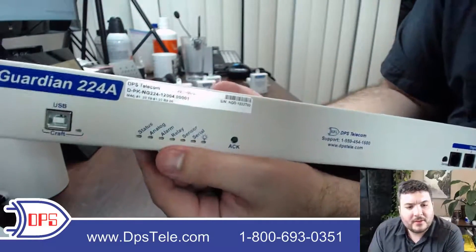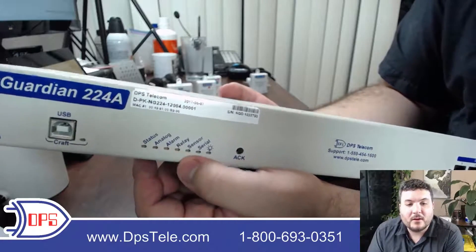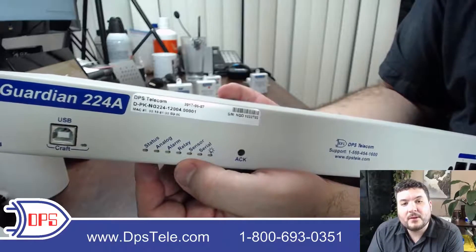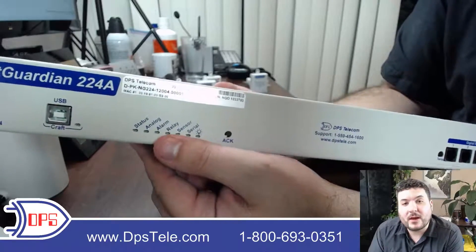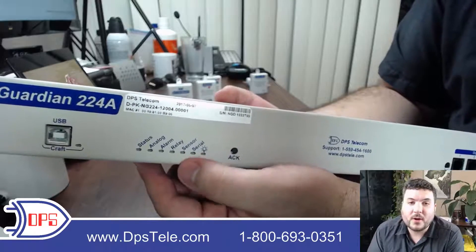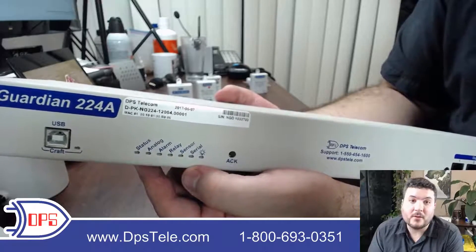Then we have some LEDs on the front panel. These will tell you if you have a new alarm, if an analog sensor has a threshold alarm, or if your control relays are operating. They first start blinking, and then if you tap the ACK button when you're out at the site the blinking will stop. It'll stay lit so you know you still have something active, but you're telling the device you got it. This way if something changes again it can start blinking again and you'll notice that it's something new.